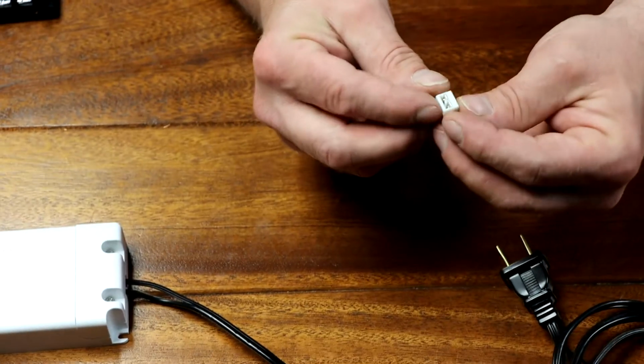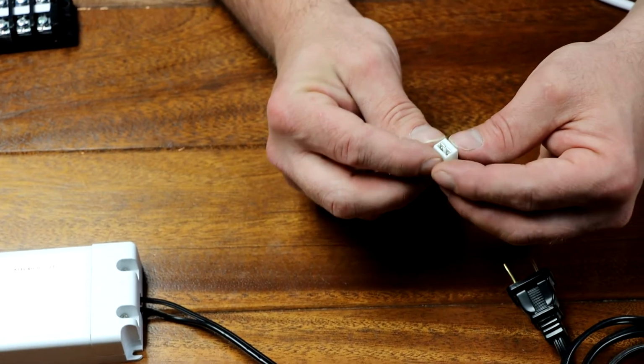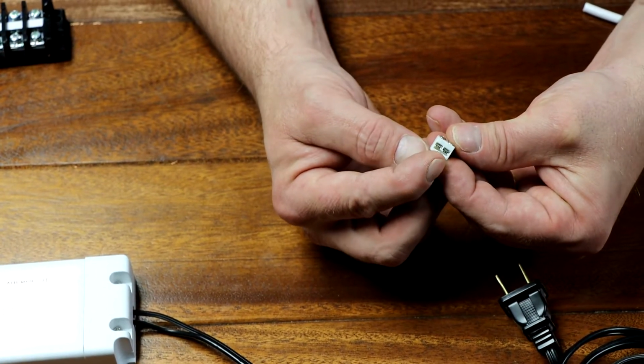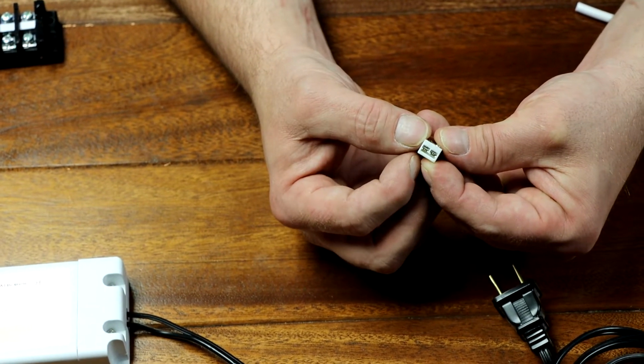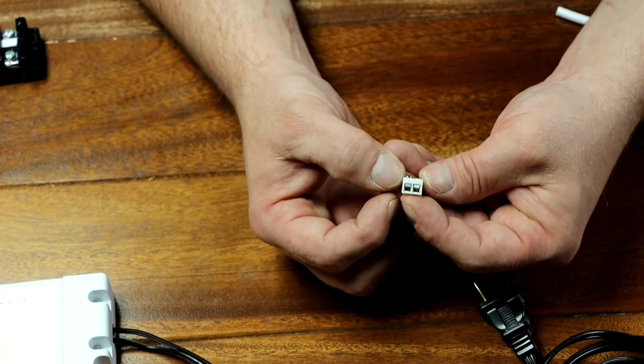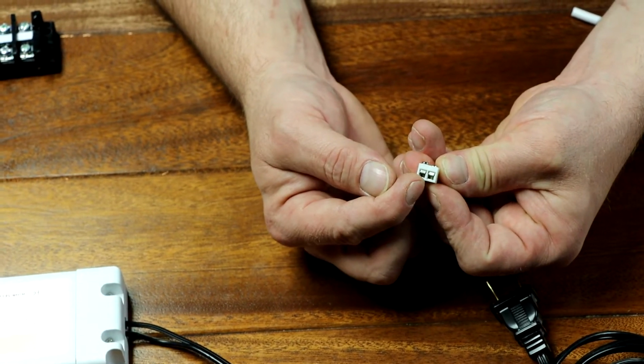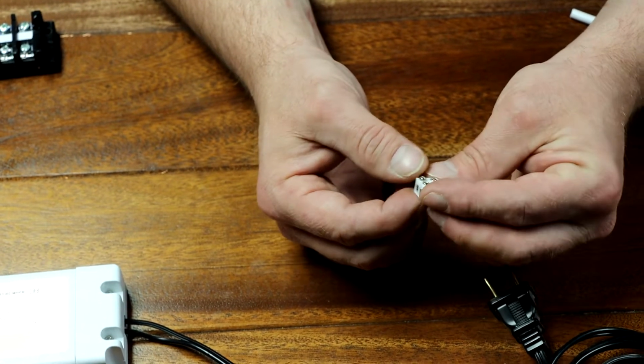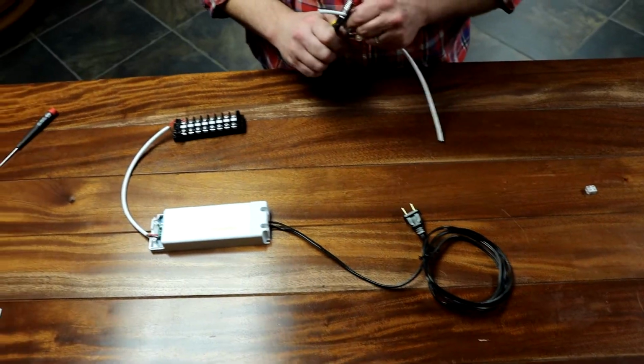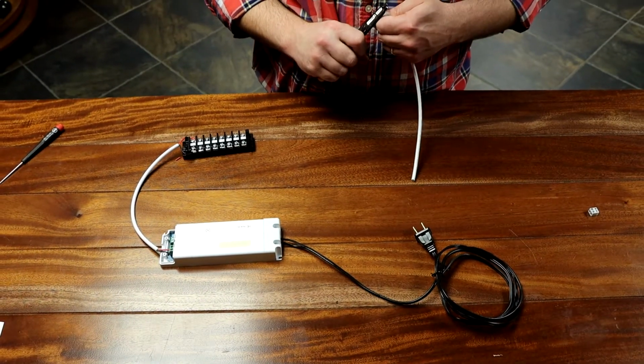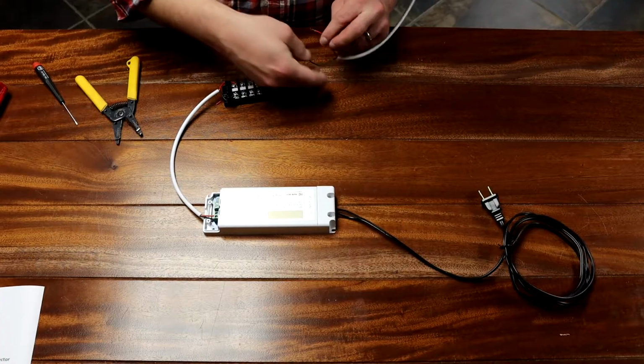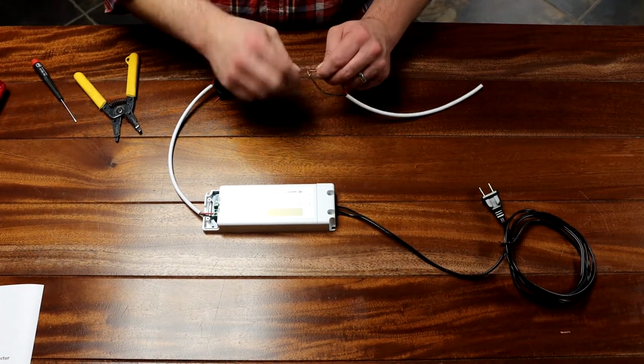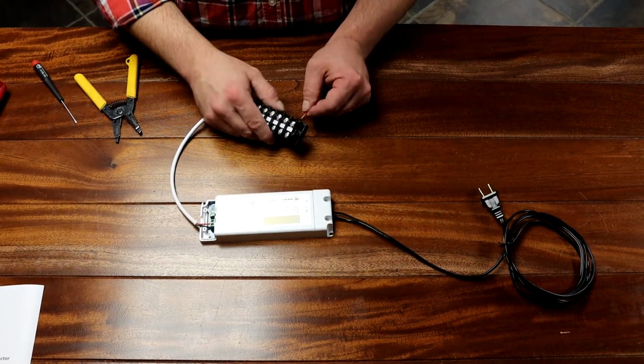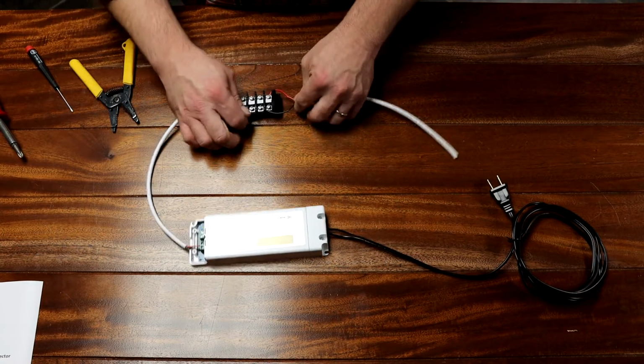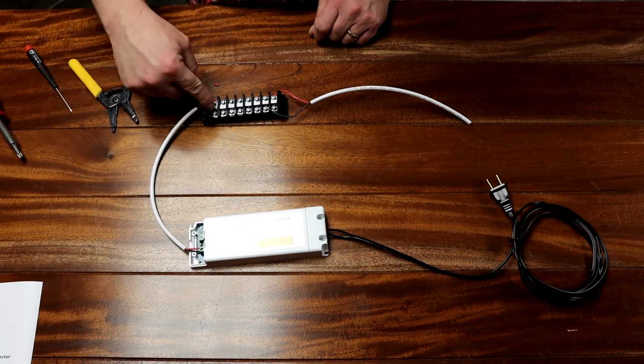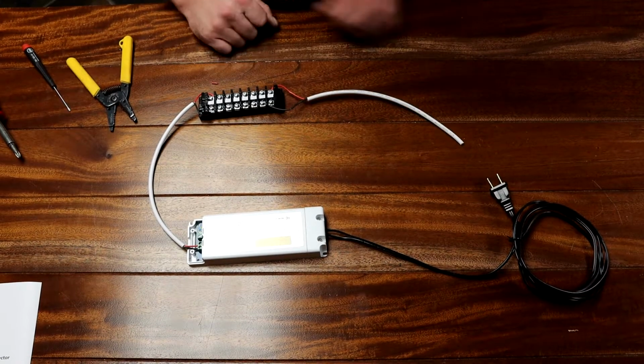If you're interested in dimming down to 0 to 10 volt, you'll use this terminal block with negative and positive indicated on the board. Next up, locate your splice kits. You'll note that one side of the splice kit has a small groove at the bottom of it. This is what will receive the tape. Rotating around, you will see the difference. This is the side that will receive the wire. Tape side, wire side. We're going to strip the sheathing, strip the wire, loosen a series of terminals, and splice each positive and negative wire onto the appropriate side of the terminal block. Tighten your screws to secure the wire. We now have power coming in from the transformer and power coming out to our lighting system.